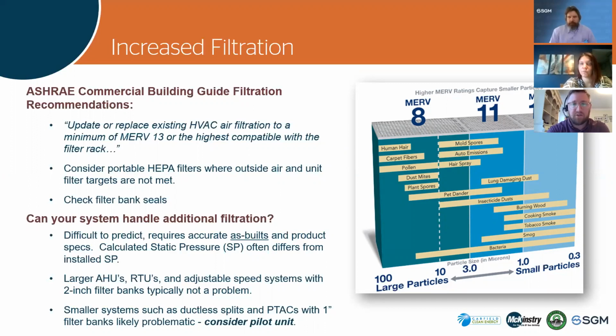What we've seen is larger air handling units, rooftop units, anything with adjustable speed probably can accommodate it, especially anything with a 2-inch filter bank. Where we have seen issues is VRF systems, little ductless splits. These have a washable filter, and unless they were actually specified with an additional filter bank, it's likely that you won't be able to increase the MERV rating much on these. And you can test it. You can take a pilot unit, throw a filter in before you buy filters across your facilities and test it.